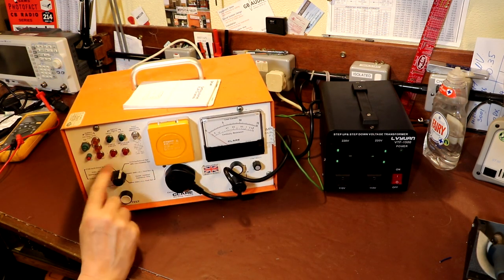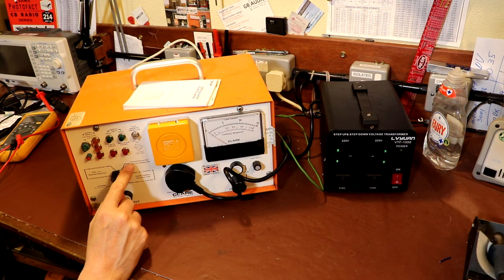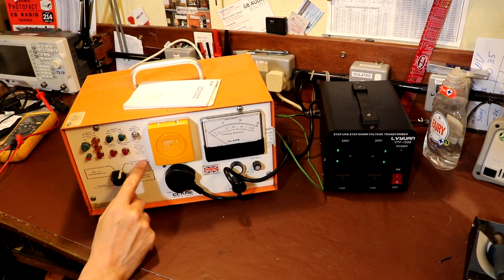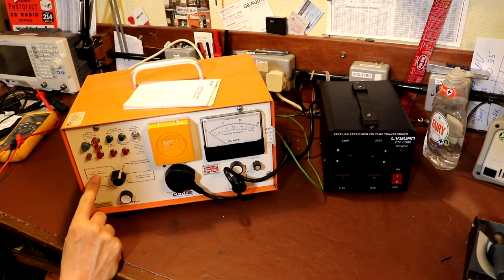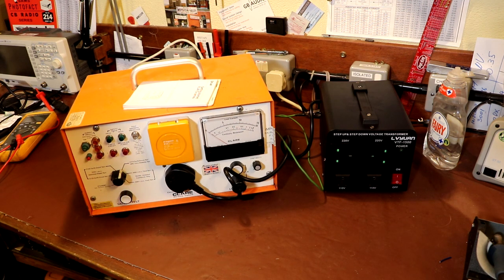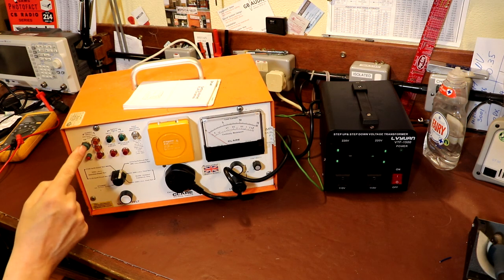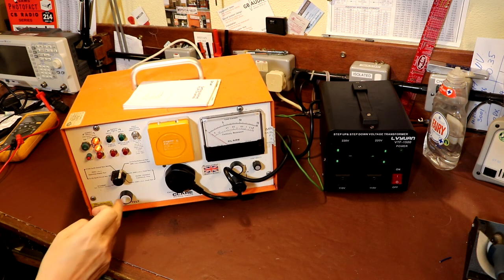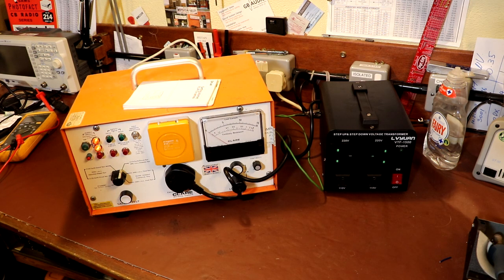So my Clare tester here has a couple of different ranges we can use. It has this 0.5 ohm for earth circuit test, and it does that at 500 volts for insulation. And then it's got another setting over here where it actually looks for a higher safety standard, so it's looking for less than 0.1 of an ohm for our earth cable, and it's going to do the flash test at 1250 volts. But let's see if it passes the lower test first. So it passed that, no problem.